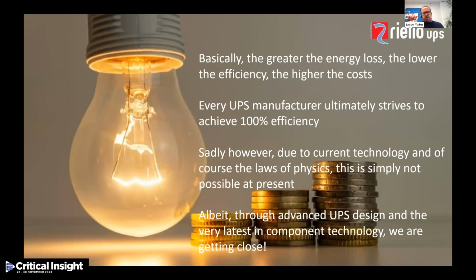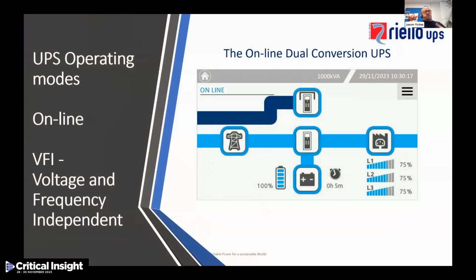Before we start looking at the effects of efficiency, I just want to explain exactly how an online dual conversion UPS works and why efficiency is so important. On the screen you can see a typical diagram of an online dual conversion UPS system. On the left-hand side, you've got the main supply input. On the right-hand side, you've got the output to the load. At the bottom, you've got the batteries, which provide power to the UPS when the main supply fails. At the top, you have the bypass line, which can be used for various operating modes during emergencies or during maintenance periods. The system is referred to as the online dual conversion or online double conversion UPS. The term dual conversion comes from what we do within the UPS system.